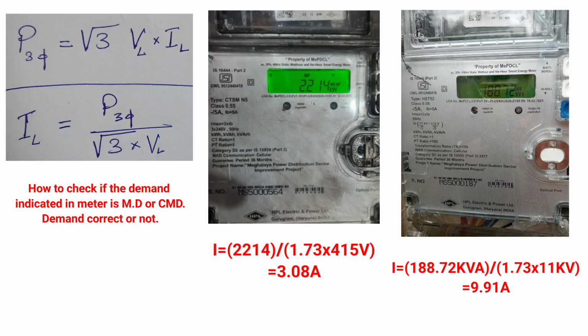For example, in the first case, the demand indicated by the meter is 2.214 kW, and if we express it in watt, it will be 2214 watt. We divide this by 1.73, which is nothing but root 3, into the line voltage 415 volt, as this is a case of LT voltage. Everything is based on the three-phase formula you see on the top left corner: three-phase power is equal to root 3 into line voltage into IL. If we take phase to neutral parameters, we just multiply by factor 3, but since we are taking line to line, we multiply by root 3.